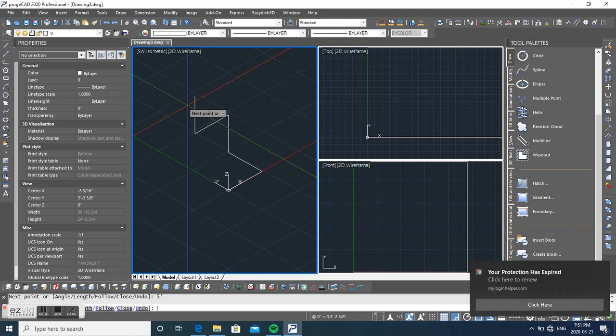A minimum of 12 inches, of course. That is based on our code and based on the client standard. Some client standard wants a minimum of 24 inches in radius, especially those fiber optics.